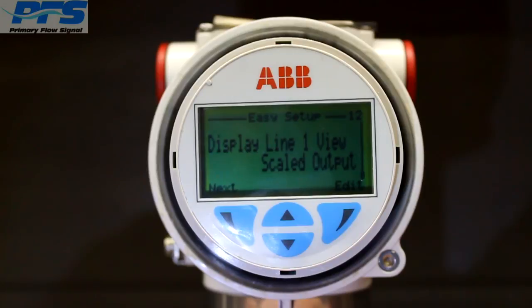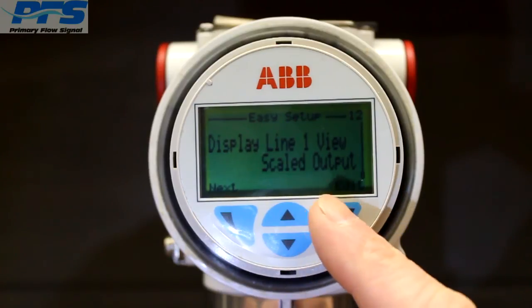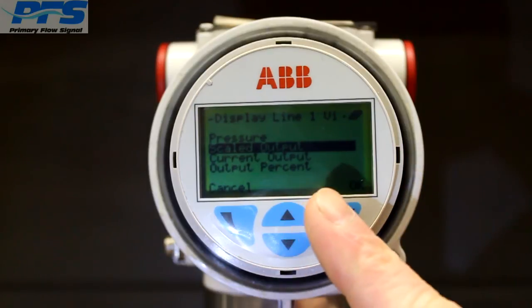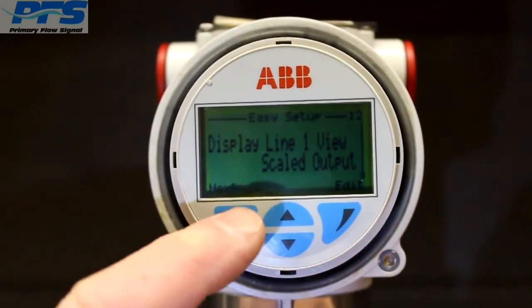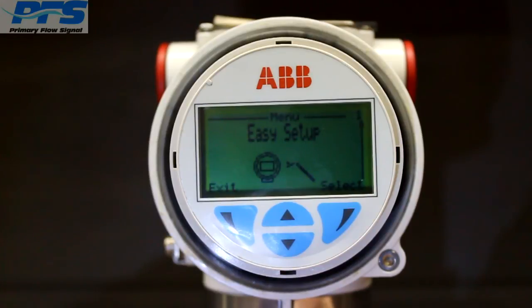Now we've got display setup here. Line 1 view is scaled output. If we edit, it gives you the options here. You can show the differential pressure that you're reading, scaled output, current output, so it would be your milliamp output, or your output percent. We're going to leave that at scaled output and hit next, and then that's it. There you go.